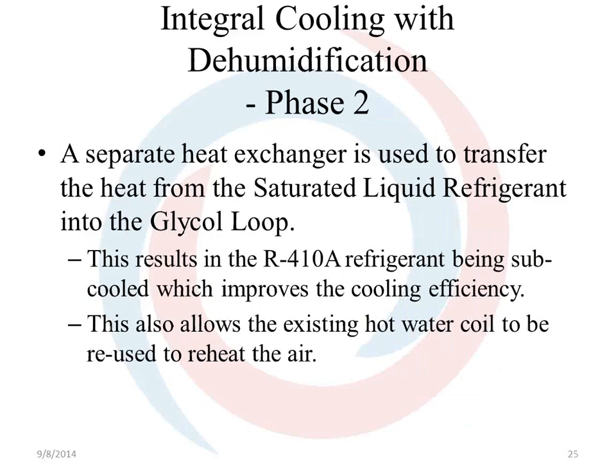So what that's going to help you do is if you want to dehumidify the supply air, let's say from 95 to 76, it needs to be first cooled to around 49 to remove the moisture. Then you've got to heat it up to about 58 before leaving the unit. Normally this would require an additional 1 to 2 row hot gas reheat coil. The drawback is that an additional coil increases the internal static pressure drop and therefore the brake horsepower, the amp draw, and everything else.